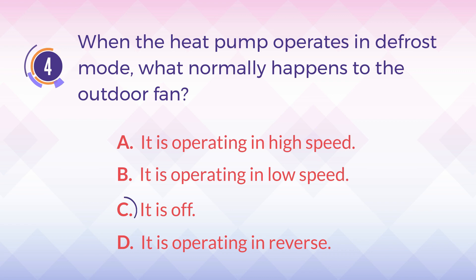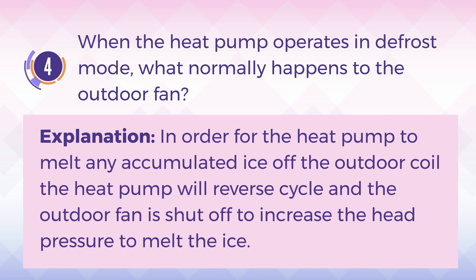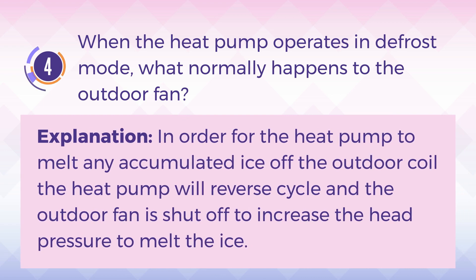The answer is C, it is off. Explanation: In order for the heat pump to melt any accumulated ice off the outdoor coil, the heat pump will reverse cycle, and the outdoor fan is shut off to increase the head pressure to melt the ice.